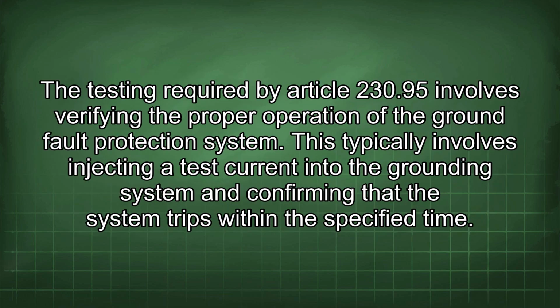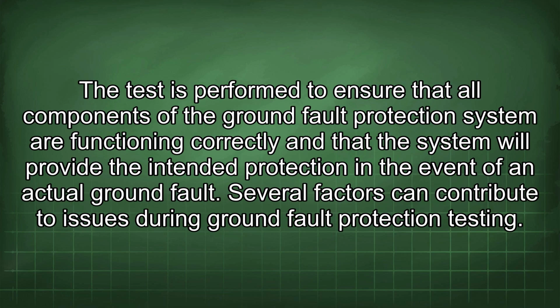The testing required by Article 230.95 involves verifying the proper operation of the ground fault protection system. This typically involves injecting a test current into the grounding system and confirming that the system trips within the specified time. The test is performed to ensure that all components of the ground fault protection system are functioning correctly and that the system will provide the intended protection in the event of an actual ground fault.